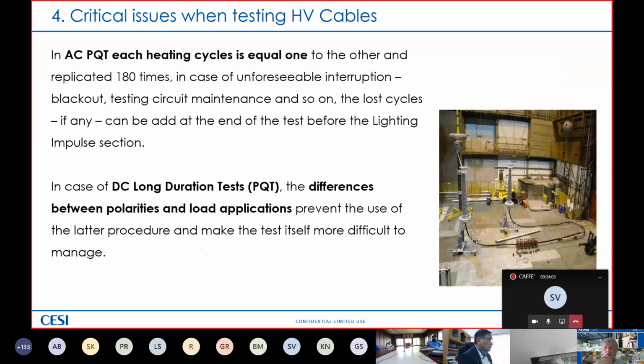We can compare some critical issues between an AC PQ test and a DC long duration test or PQ test, as you like. During an AC PQ test, each heating cycle is equal one to the other, and it is replicated 180 times. So in case of unforeseeable interruption, blackout, testing circuit maintenance, and so on, if you lost a cycle, you can add it at the end of the test before going to the lightning impulse section. So sometimes instead of 1 year, the test lasts for 1 year and 1 week, 1 year and 10 days, 1 year and 3 days. But it's not a problem because you put the test to be performed at the end. Every cycle is equal one to the other, so no problem.